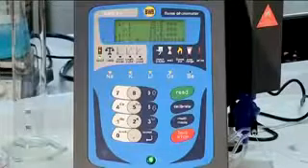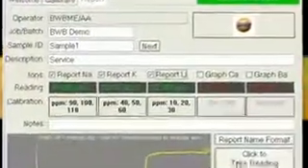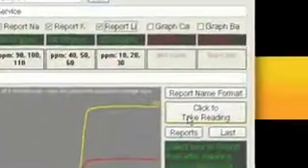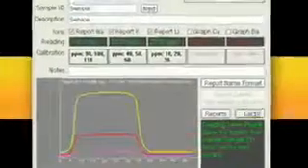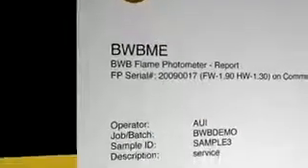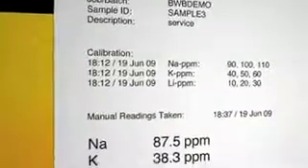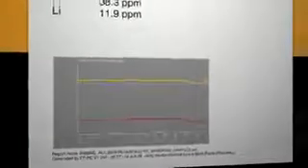Click on the format button to open these preferences. You have a variety of settings available to you during setup which allow you to further customize your XP experience, including report names and report layouts. Close the box. Tick the ion box to watch it on the 1 minute graph. Any or all of the ions can be graphed as long as they are calibrated. The 1 minute graph is continually updated so you can monitor the instrument and see when stability is achieved.